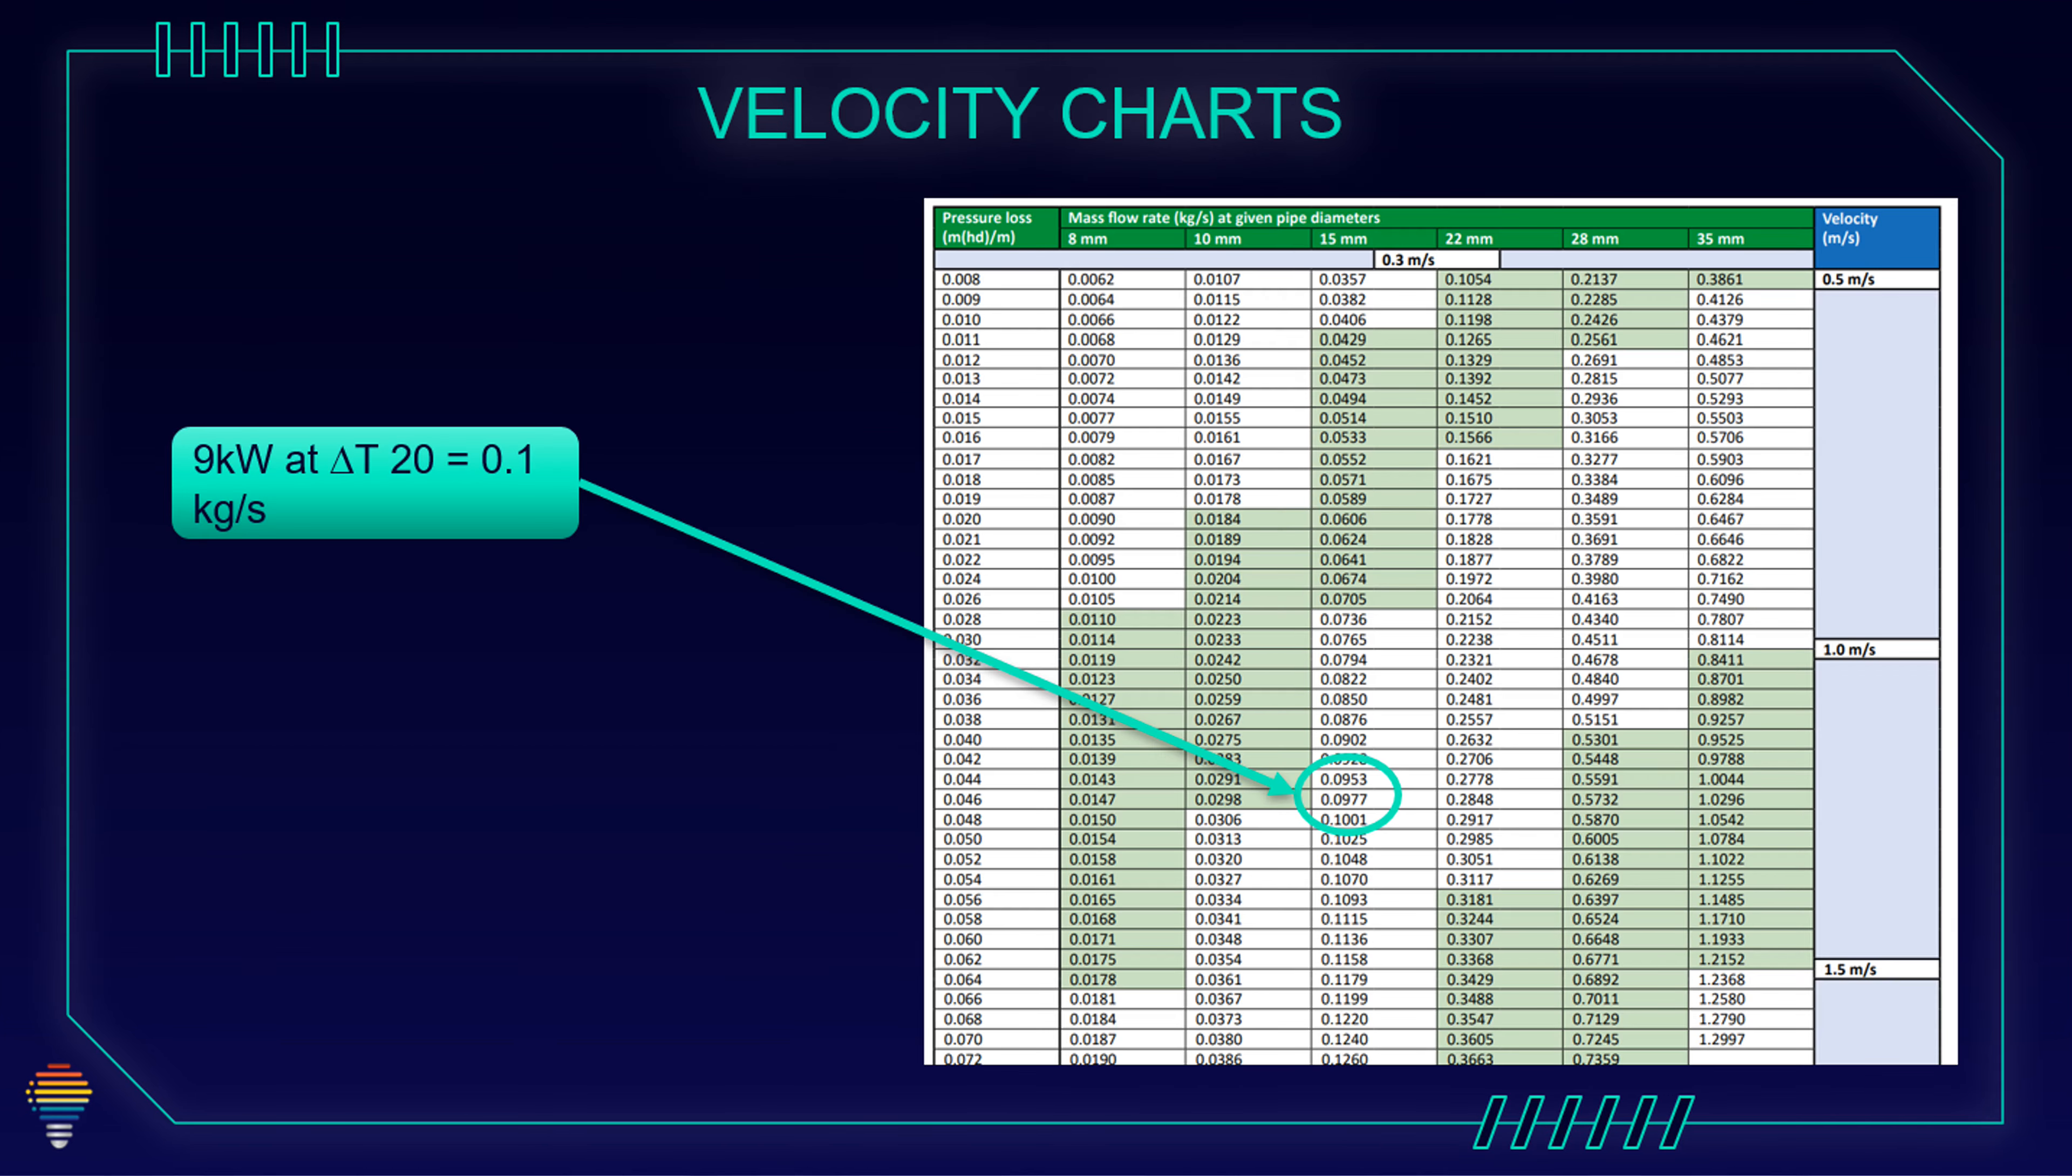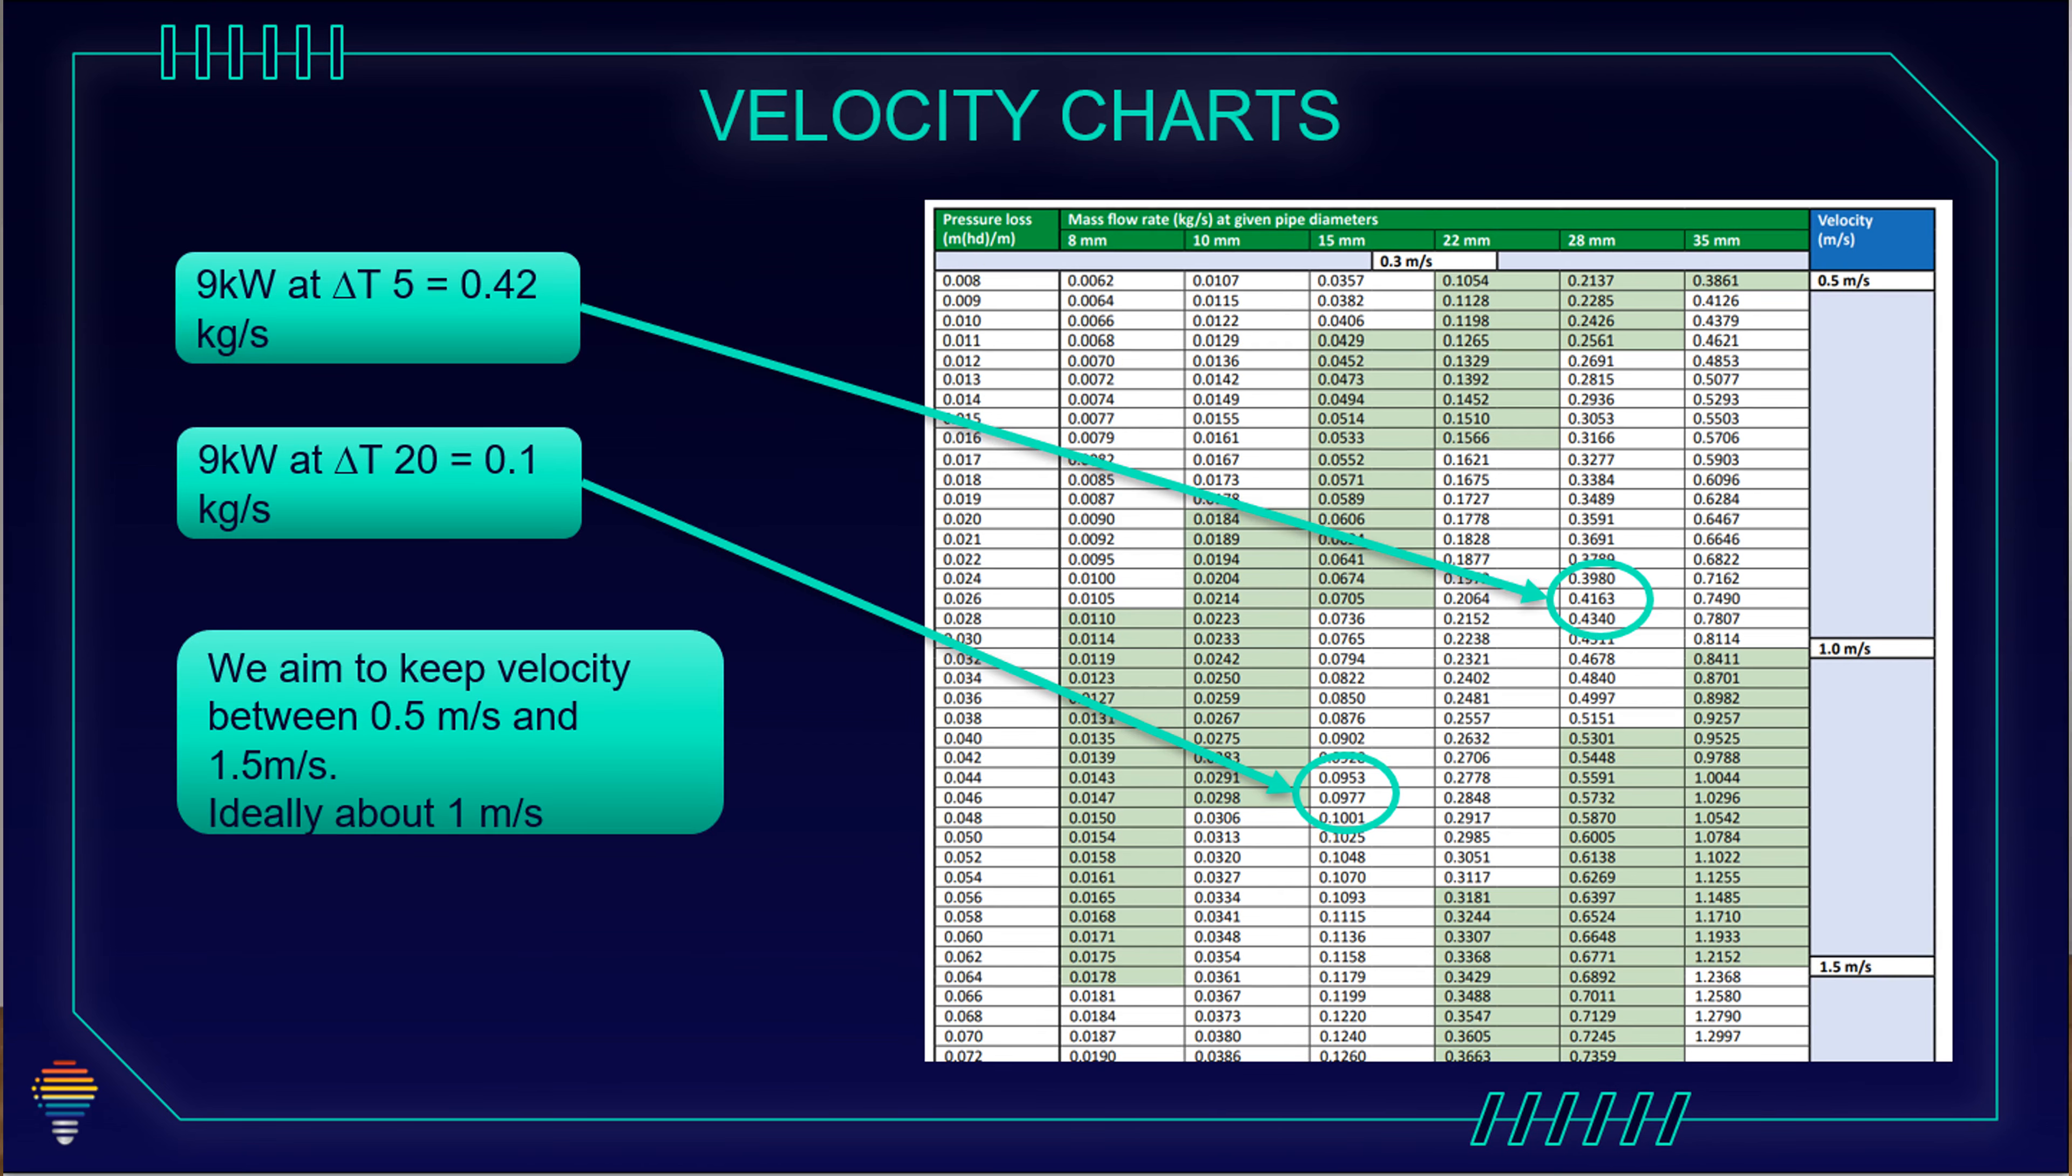But for delta T 20, as example, our gas condensing boiler, our flow rate is 0.1 kilogram per second, we need to go with pipe diameter of 15 millimeters. So for heat pump, it's 28. If we have bigger delta T, we could go with lower pipe diameter. This is if we want to have our ideal velocity around one meter per second.